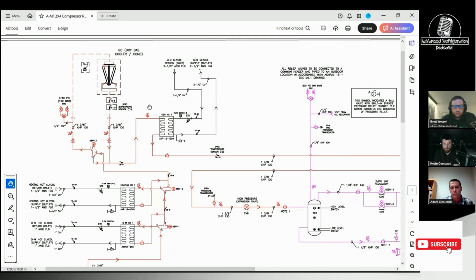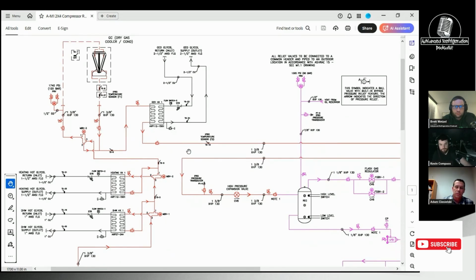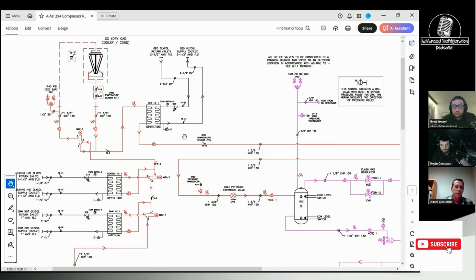And then any residual heat, then this becomes a subcooler. So we're using the ground source, the geoglycol loop, then to cool this further. So what's neat about this is it was 95 to 100 degrees this summer, and we were still running 70-degree condensing temperature. So very efficient. It allows the compressors never to even get close. I know people talk about an adiabatic condenser, about not running transcritical, but in all reality, they are running 85-degree gas cooler out, and essentially that is a transcritical.